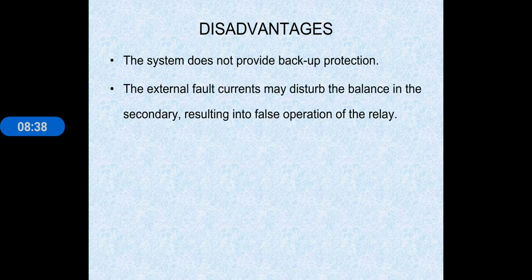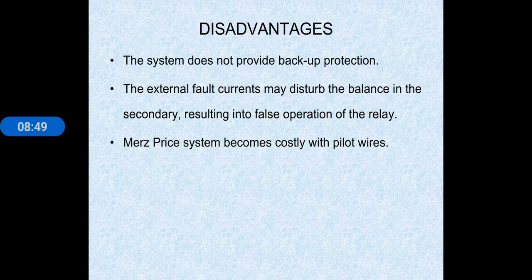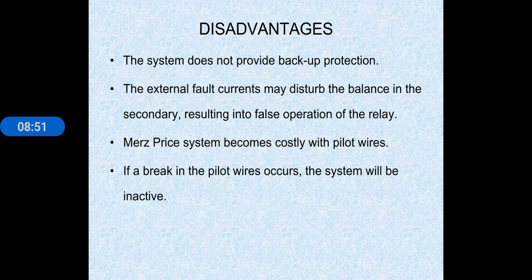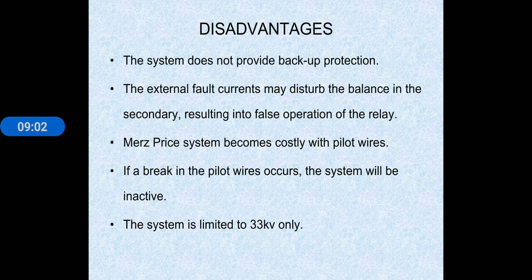It doesn't contain any backup protection. Also, external currents may disturb the balance in the secondary, resulting in false operation of the relay. If any external fault occurs, it may disturb the balance in the secondary, and it results in failure of relay operation.